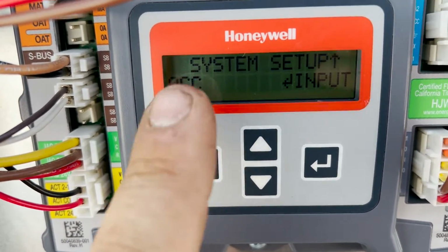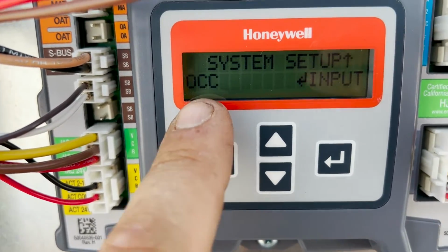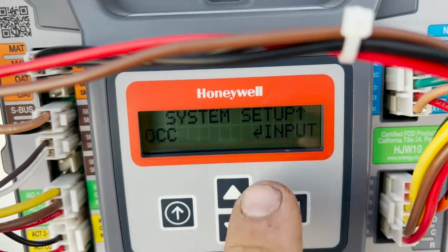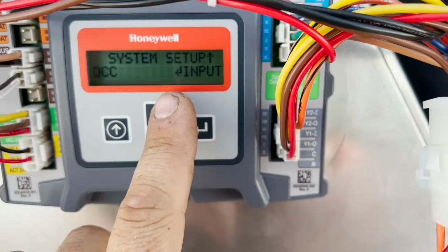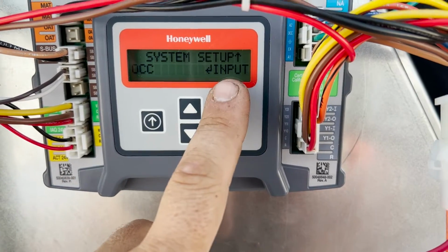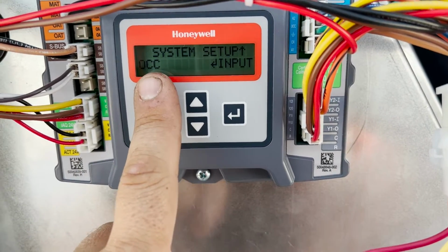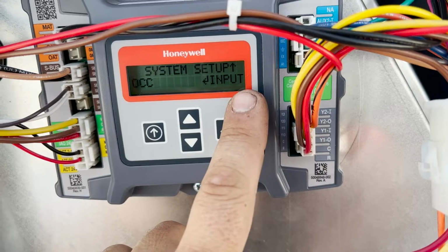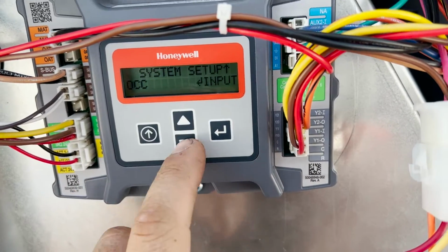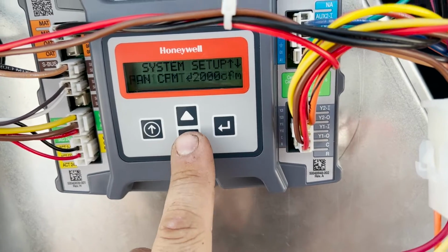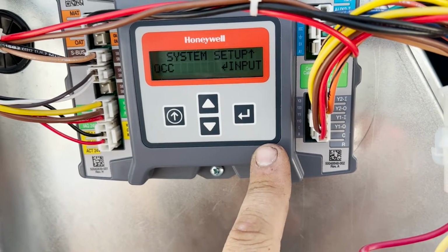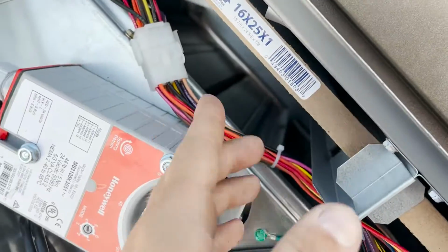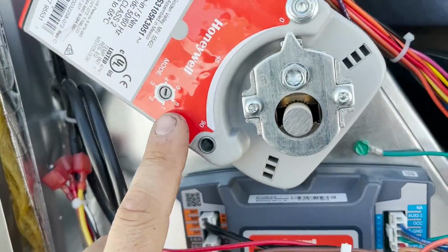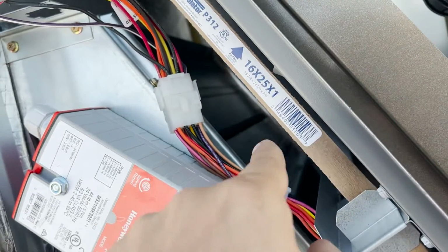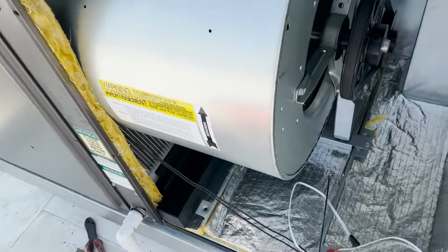Occupied, okay? On this, where we have an occupied call from the thermostat, we're looking for an input versus always occupied. And this is going to affect our minimum outside air positions. And if the energy auditor is coming, he's going to make sure that occupied does something. So you need this economizer to be looking for input on occupied. And that's it. But if you don't run through and set this up, the air balancer is going to have a hard time doing his job because this is going to go all wily when he makes an adjustment. But also, don't forget, this needs to be in mode 1, where that'll be all the way open when you power it on.